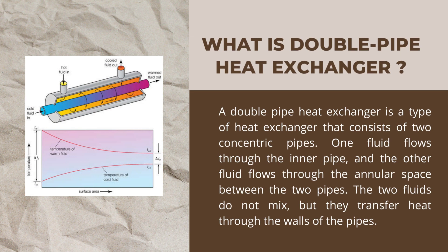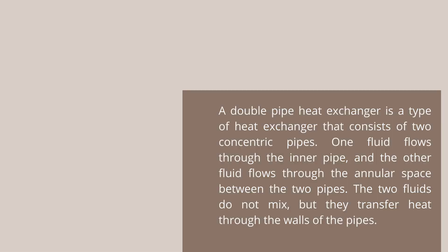A double pipe heat exchanger is a type of heat exchanger that consists of two concentric pipes. One fluid flows through the inner pipe and the other fluid flows through the annular space between the two pipes. The two fluids do not mix but transfer heat through the walls of the pipes. As shown in the photo on the right side, you can see cold fluid going in and warmed water coming out, because of the hot fluid inlet on the shell side transferring heat to the cold fluid.